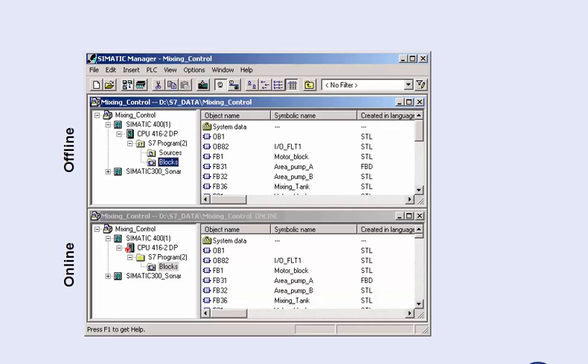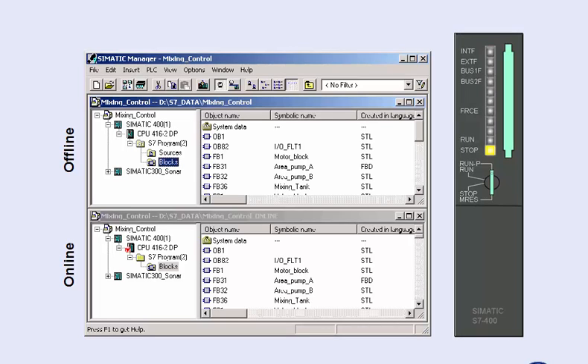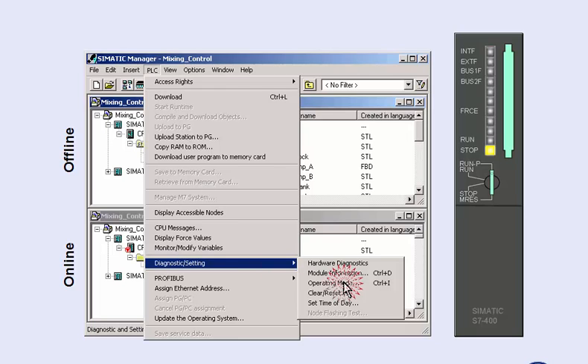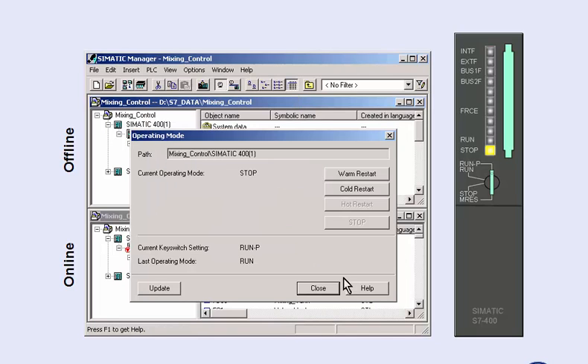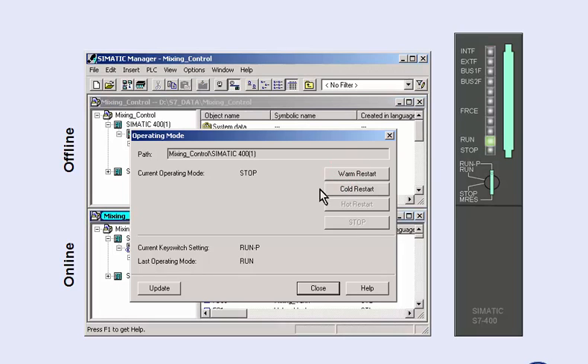To continue commissioning the software, please ensure that no dangerous machine or plant states can occur and switch the CPU to run mode. Select the dialog for the operating mode via the target system menu and start the CPU via mouse click. If the current operating mode changes to run, you can then start testing the functions. If the CPU remains in stop mode, the diagnostic buffer gives you specific information on the cause of the error.